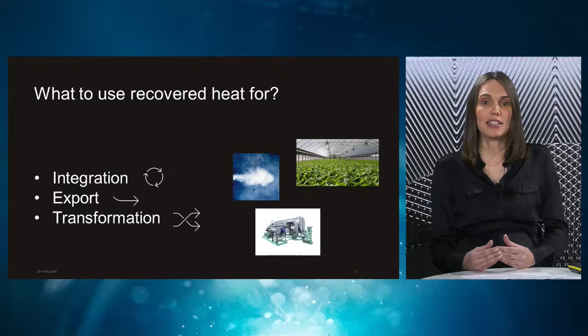Now we know where to find the heat and what we can use it for. So how do we ensure that we make the most out of the recovered heat? Well, one crucial aspect when selecting the technology for heat recovery is the heat exchanger. And by selecting heat exchanger technology with a close temperature approach, we ensure that we keep as high grade of waste heat available also for reuse.